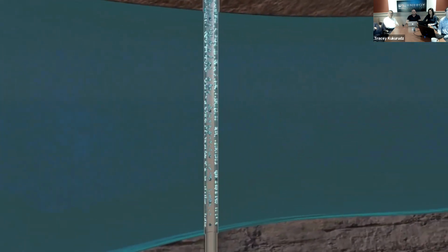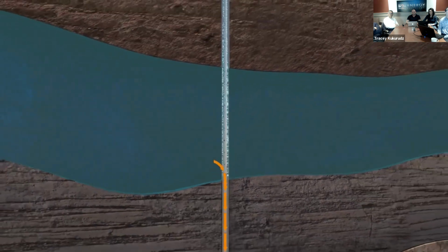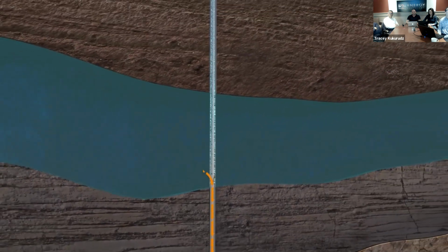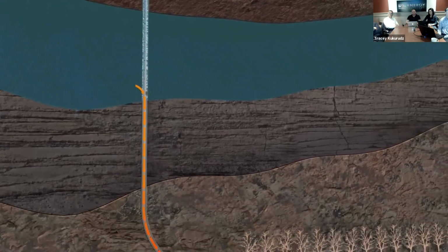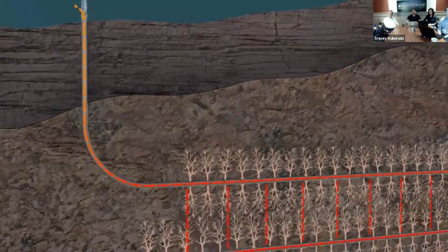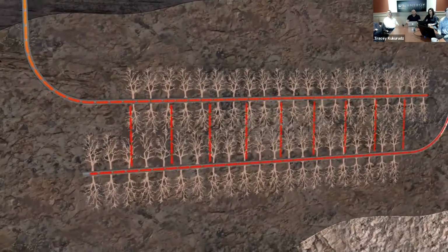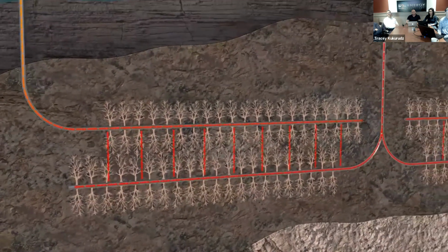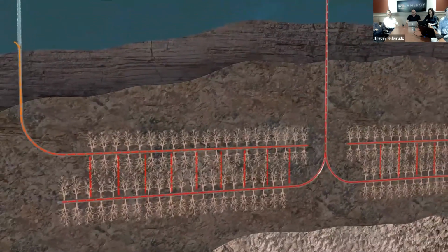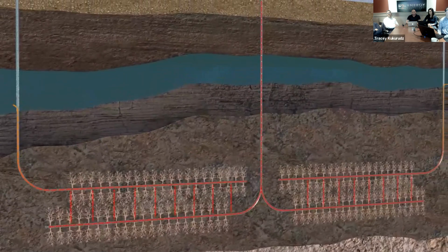As the hot reservoir brine passes through the gas recovery conduit in the reservoir, the trapped gases are liberated from the reservoir brine, which then travel up the conduit to the wellhead, where they are recovered. The remaining hot brine flows down the injection conduit to the created deep earth radiator. The hot brine then slowly flows through the fractures, where the temperature is upgraded to greater than 200 degrees Celsius and is recovered by the injection legs and brought to the surface.